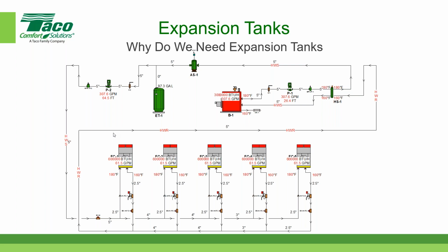But then you have to locate and mount it up there, and you need piping to get it up and down, so there are trade-offs, correct? Possibly. If you have a hot water heating system like the one on screen, with the boiler room as the main mechanical room containing the boiler and pumps, and the expansion tank is in the penthouse, then in our building example the expansion tank will wind up being physically smaller. So the higher you put the expansion tank in the building, the smaller the tank needs to be.